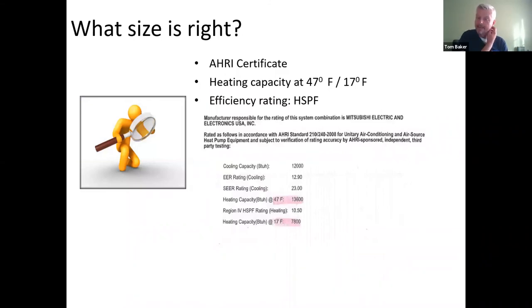And then the second part of that is when a contractor comes to your home, it's critical that they do a heat loss. We use an accredited heat loss calculation program or software that the whole industry has agreed is the most accurate. It's called ACCA, but what it does is it gives you the peace of mind that if we come in and we collect all the data on your house, square footage, ceiling height, windows, whether they're upgraded low E, insulation values in your walls, your ceiling, your attic, it's really a process. We're going to spend probably 45 minutes in your home gathering information, making sure that we understand what the needs of this home are going to be in both heating and cooling, and then we size the equipment properly.